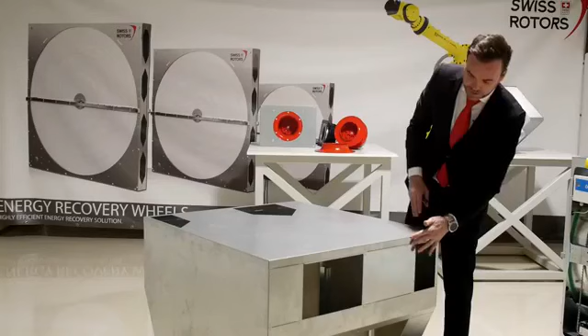On this unit, in an environment where you wanted to optimize the bypass as much as possible, you would simply fit some dampers on the face of the unit. At the top, we have a good amount of space where you could fix dampers too, and the air would flow over the top of the unit and down through two holes on this side.